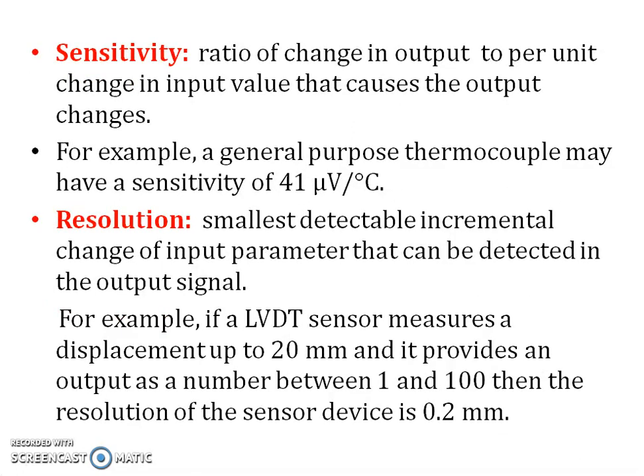Sensitivity is the ratio of change in output by unit change in the input value that causes the output to change. For example, a general purpose thermocouple may have a sensitivity of 41 microvolts per degree Celsius.